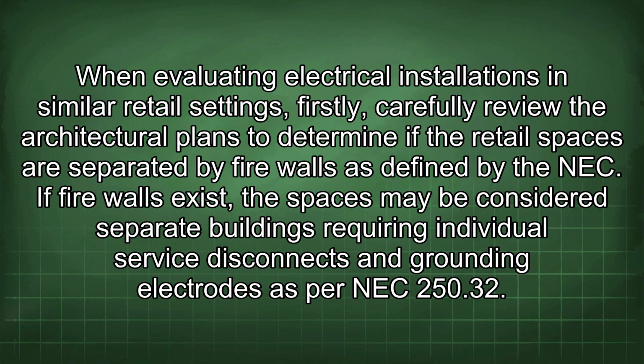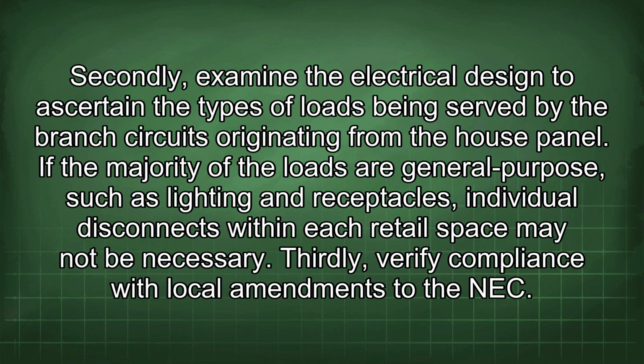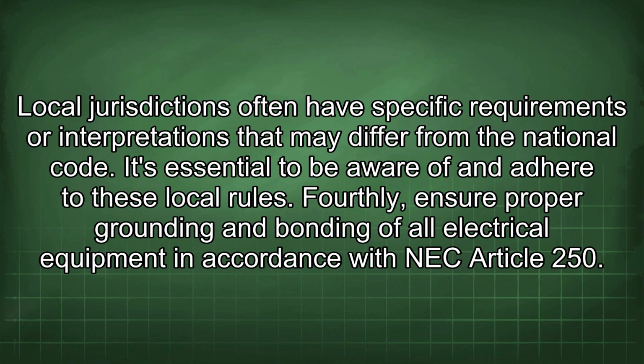When evaluating electrical installations in similar retail settings, firstly, carefully review the architectural plans to determine if the retail spaces are separated by fire walls as defined by the NEC. If fire walls exist, the spaces may be considered separate buildings requiring individual service disconnects and grounding electrodes as per NEC 250.32. Secondly, examine the electrical design to ascertain the types of loads being served by the branch circuits originating from the house panel. If the majority of the loads are general purpose, such as lighting and receptacles, individual disconnects within each retail space may not be necessary. Thirdly, verify compliance with local amendments to the NEC. Local jurisdictions often have specific requirements or interpretations that may differ from the national code. It's essential to be aware of and adhere to these local rules.